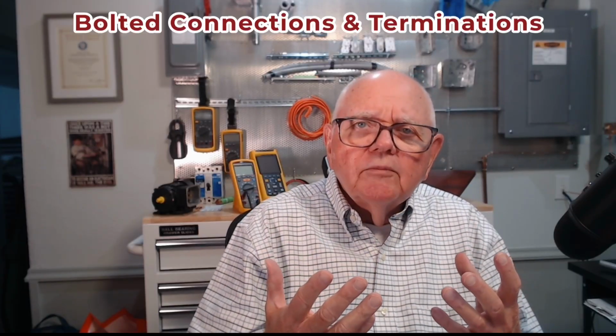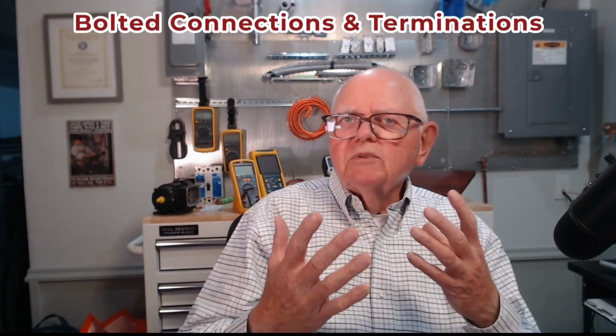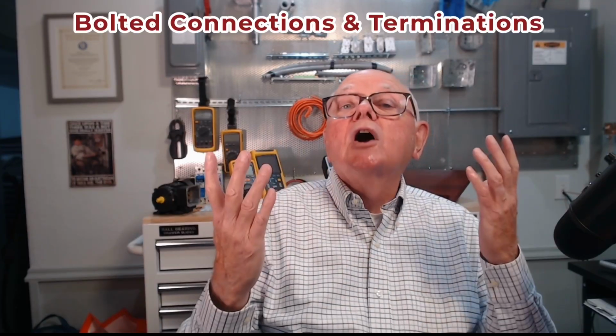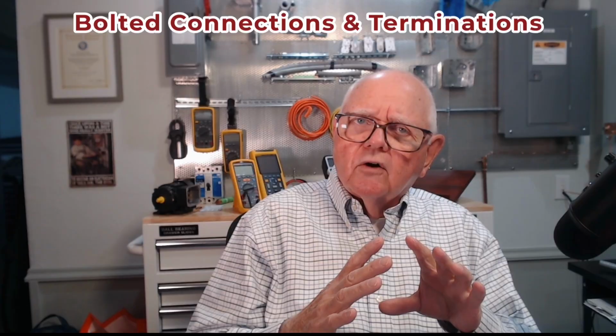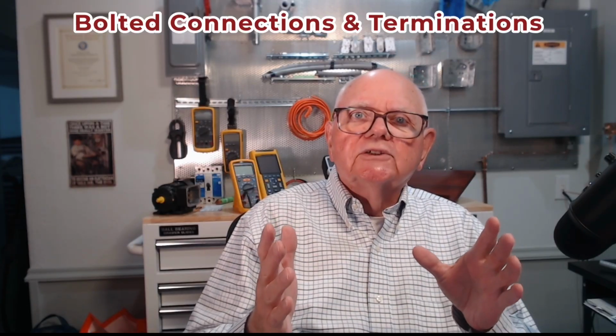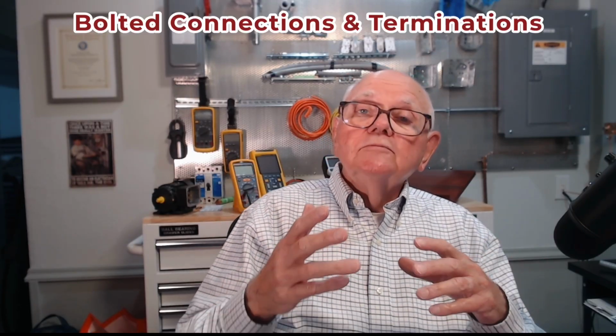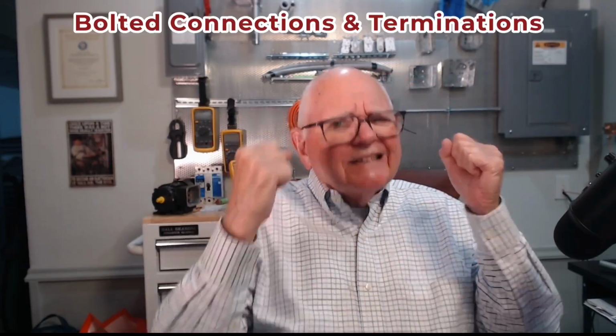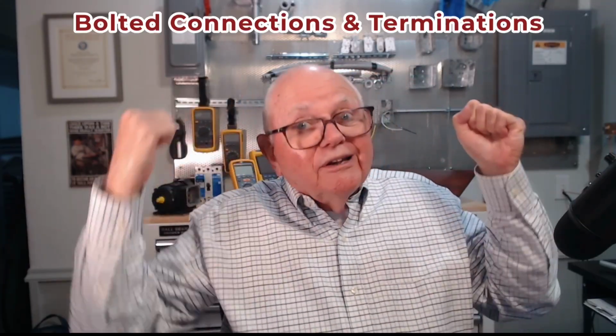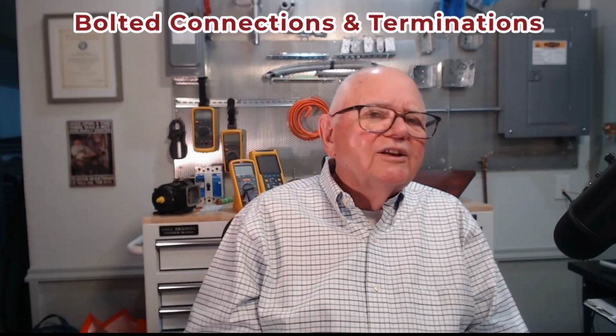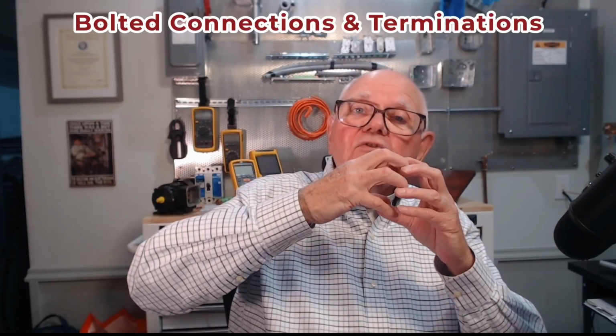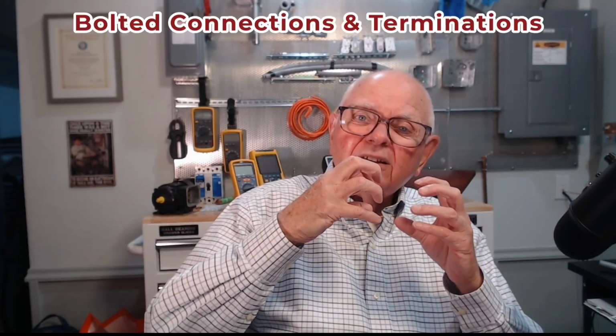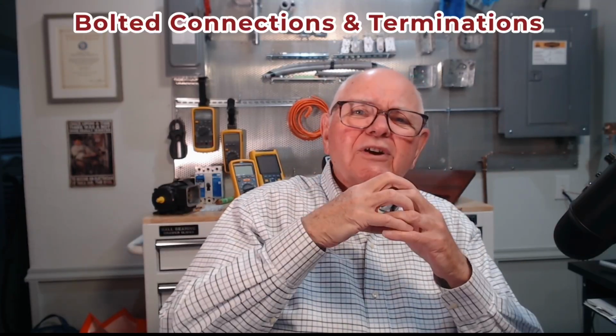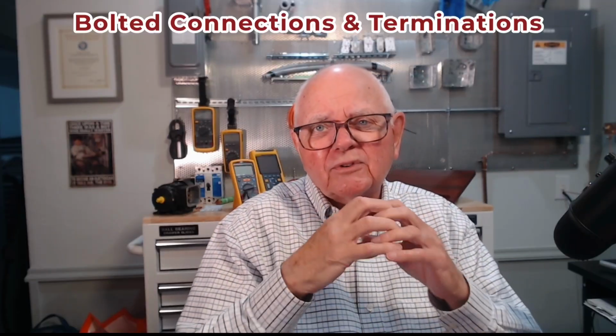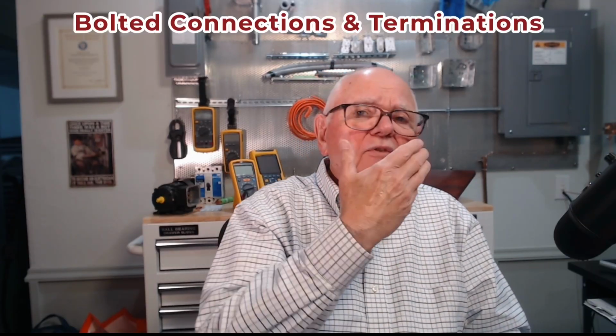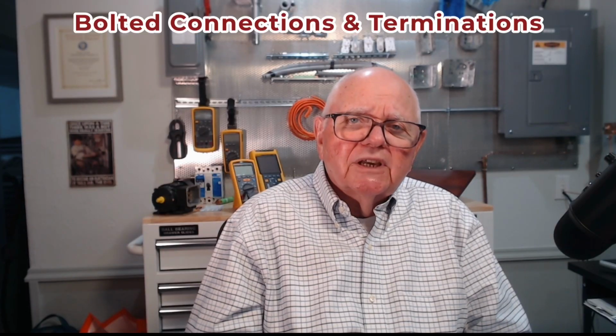If I under-tighten them, the problem is obvious. Too much resistance. Small increase in resistance, large increase in heat for the same amount of current flow. So I don't want loose terminal connections anywhere in my system. Also, if I over-tighten them, you might say, I can get them good and stuck. Man, I'll put a cheater bar on this wrench, right? That'll get it, by golly. No, you don't want to do that either. Why? If I tighten those threads that tight, I'm going to stretch them out. And if I stretch them out, it's not going to be as secure a connection as if I had them tightened to their proper torque value. So I want to follow whatever foot-pounds of torque it is for those particular terminals.